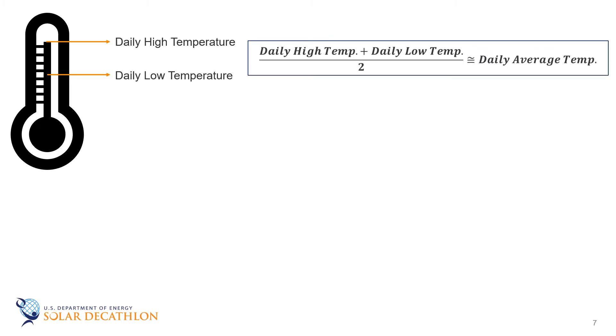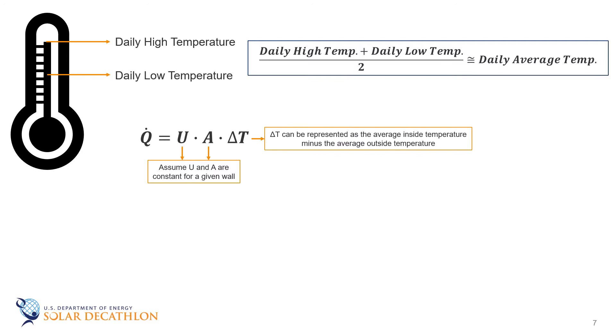When we think of our Q dot equation, if the value of U and A are constant, which is not a bad assumption, and if the wall has minimal thermal mass to store heat, then the delta T can be represented by an average temperature difference. This is quite a long list of ifs. Therefore, we will approximate the delta T of the average inside temperature minus the average outside temperature over the course of a day.